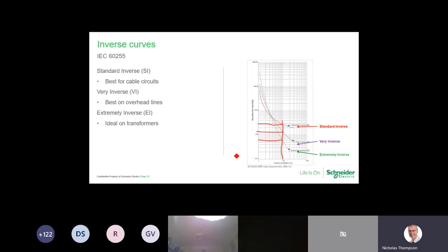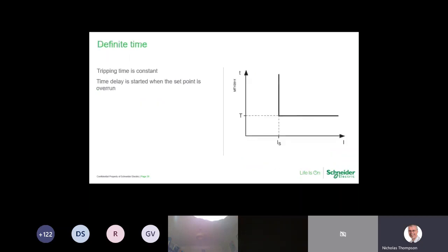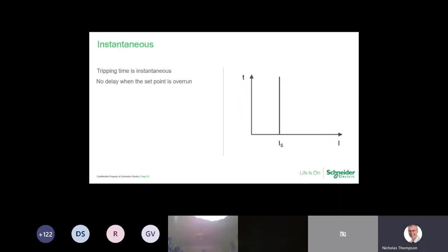There are 2 other tripping characteristics that can be employed. One of them is definite time. So here we have a tripping time which we set. We will also have a set point for the current. This is the set point current. So that's going to be a constant tripping time, irrespective of what the current is going to be over and above the set point. So this will be a constant time there, irrespective of how high the current is going to be.